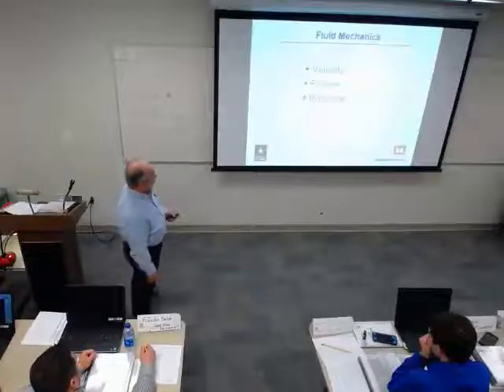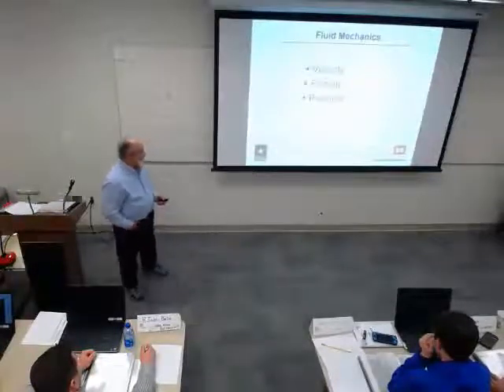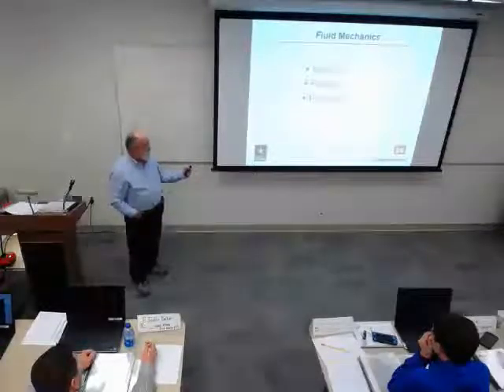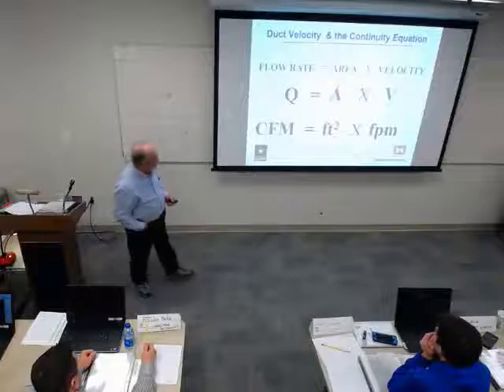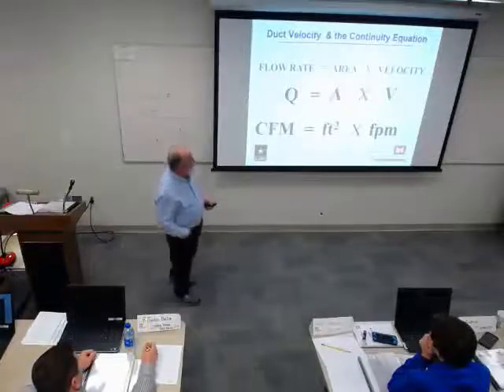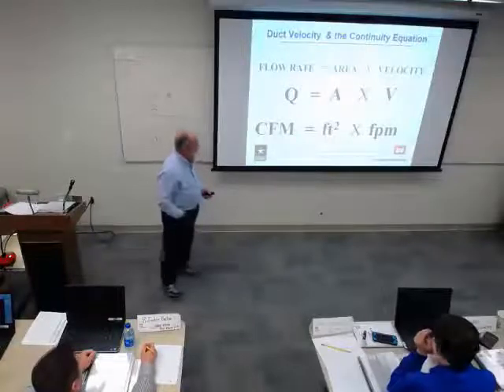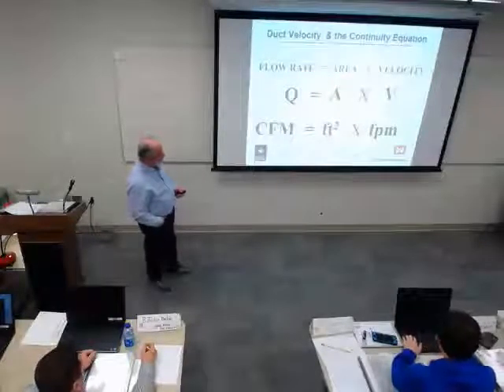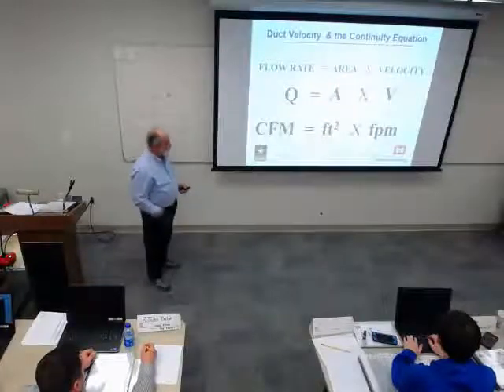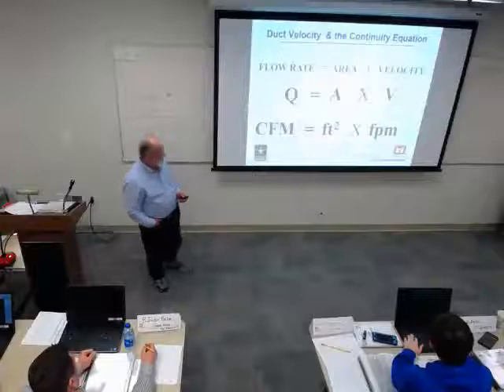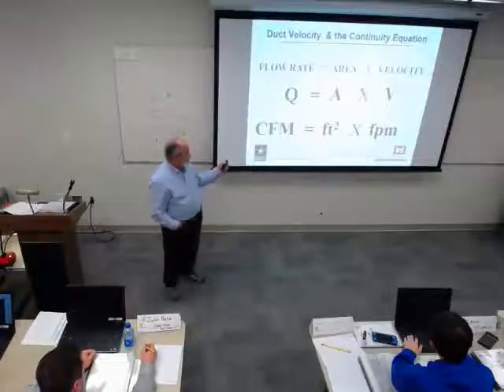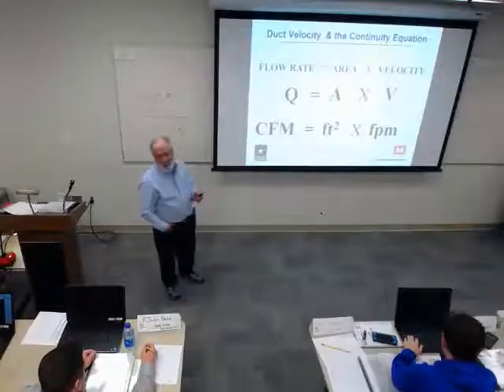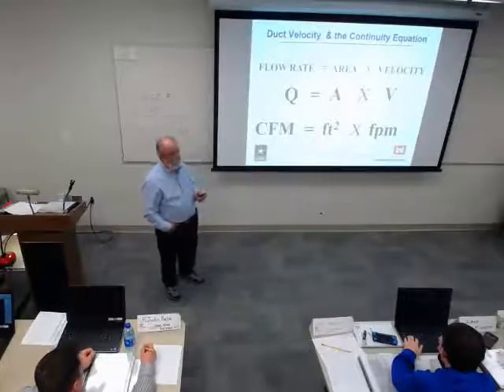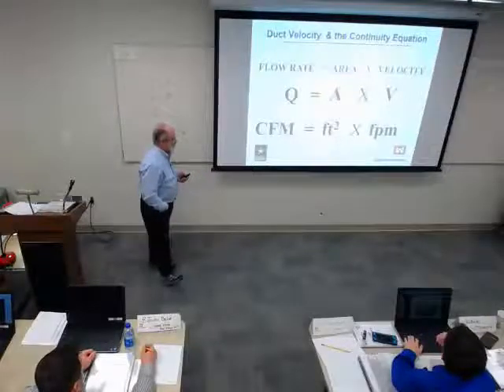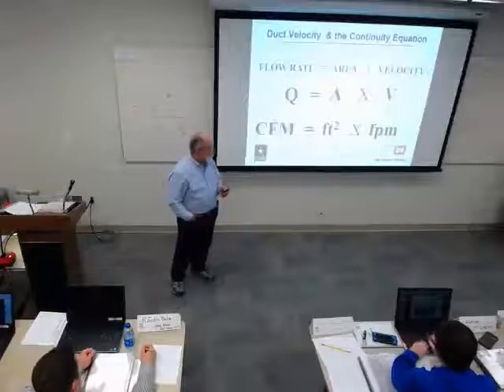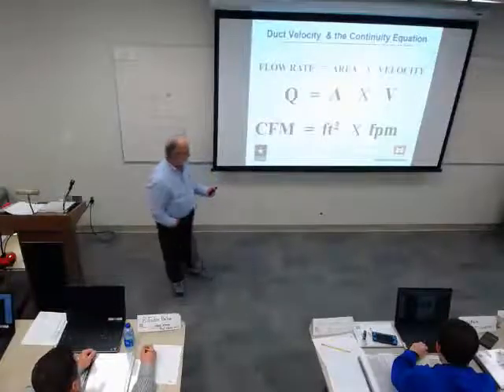I really like it. In fluid mechanics, we're pretty much sticking with velocity, friction, and pressure. That's as deep as we're going to dive, and it's stuff that we measure. Flow rate is equal to the area times the velocity. If we have cubic feet per minute, CFM, to find that, we multiply the square feet of area the air is moving through by the feet per minute. So cubic feet per minute is equal to the area of the duct cross-section times the feet per minute of the air moving through it.